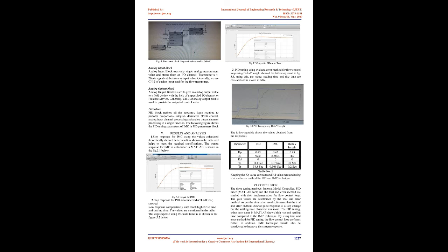Fig. 3. Step response of the system. This graph is recorded in process history view in DeltaV of real-time experimentation in open loop. To find the transfer function of open loop system, above graph is used. Calculate the transfer function by 63.3% approach of process variable. Following is the transfer function of the system. After finding out the transfer function, the values of Kp, Tp are obtained, and finding out the PID tuning parameters in MATLAB, using following method.